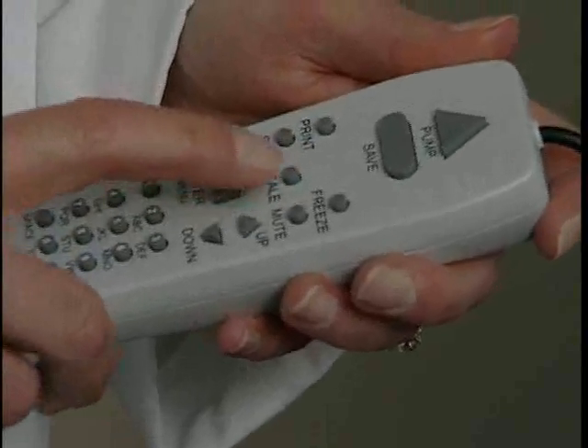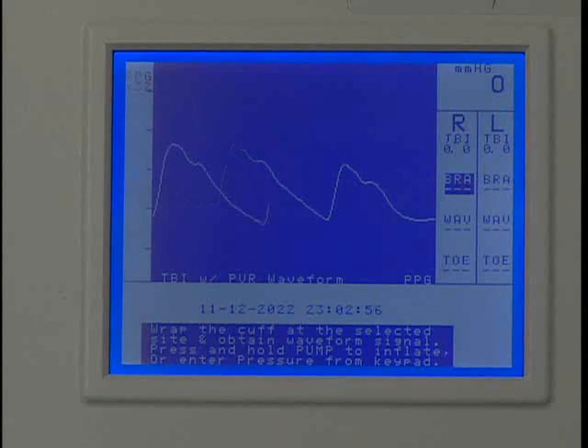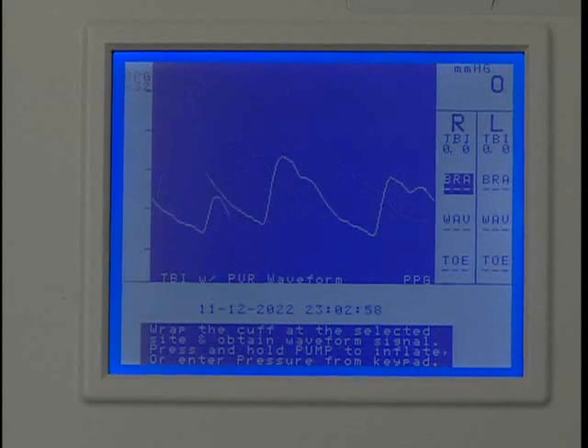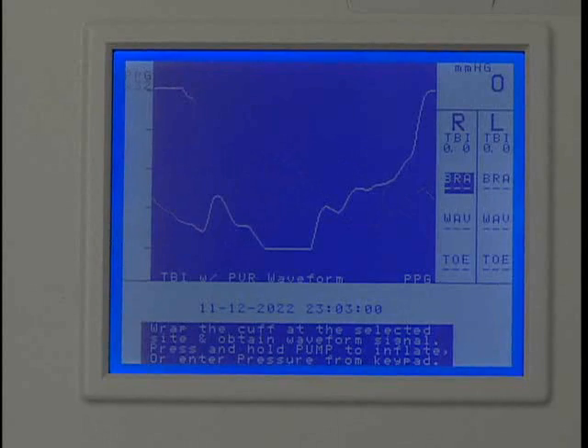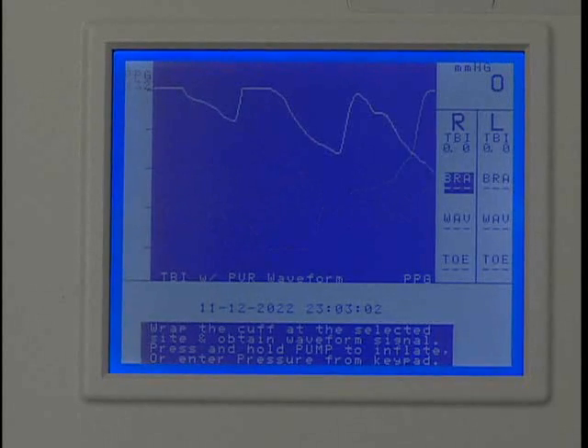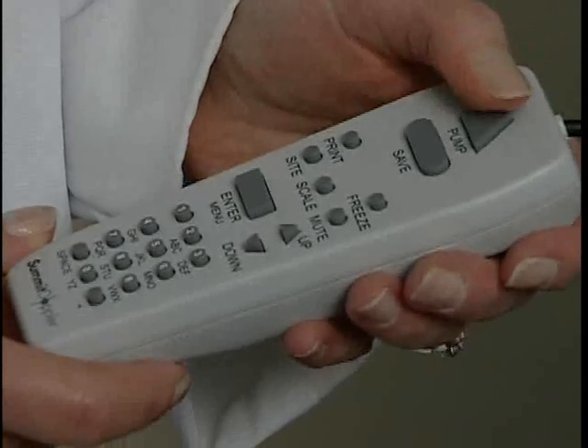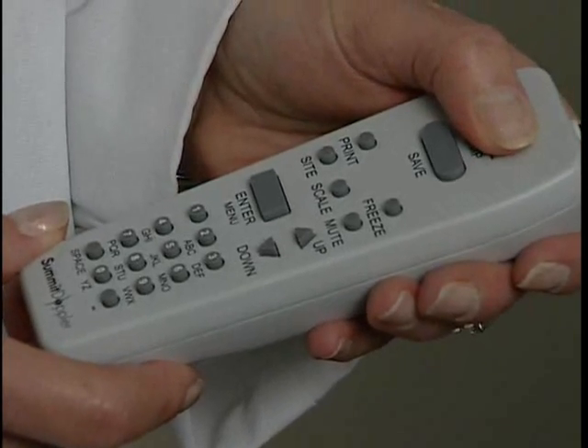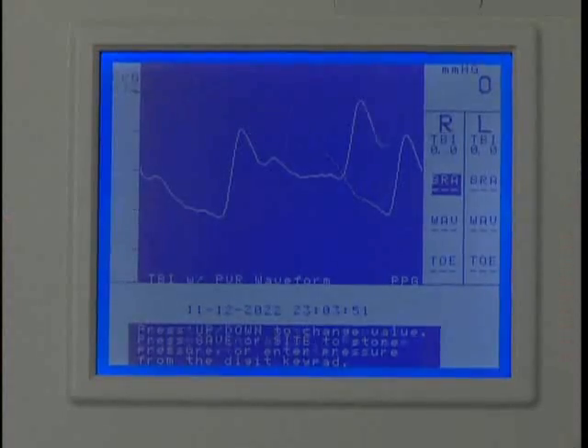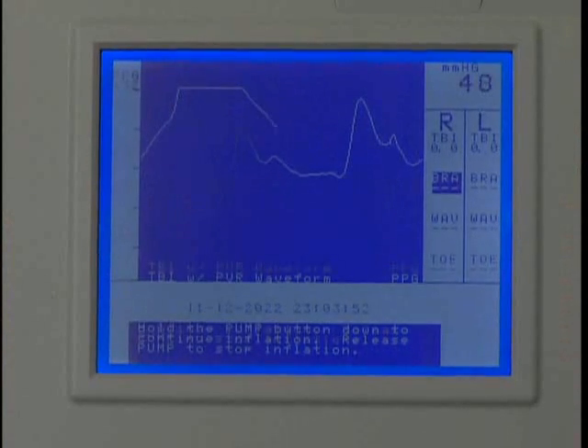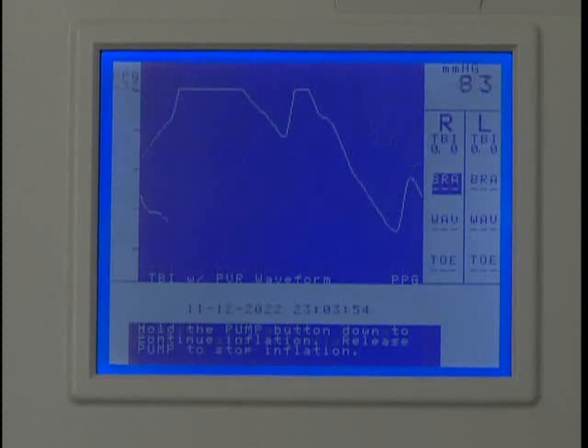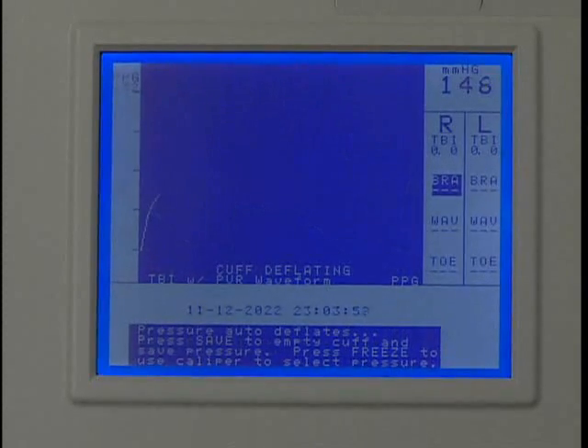Press Scale one or more times as needed to adjust the vertical scaling to obtain a waveform as large as possible without clipping at the top. Wait a few seconds for the waveform to stabilize. Once stable, press Pump to inflate the cuff. Continue to inflate to a pressure approximately 20 millimeters of mercury above the pressure where the PPG pulsations disappear. The cuff will begin to deflate automatically once the pump stops. Press Freeze after several pulses have reappeared.